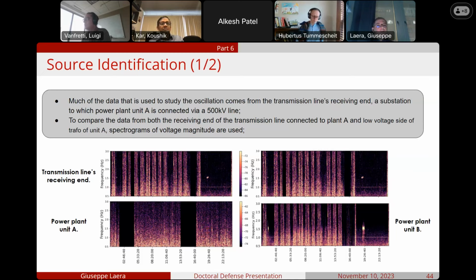So the idea to analyze the spectrogram of the voltage magnitude of unit B came out, and it was compared, as we can see here on the right, with the spectrogram again from the transmission line receiving end. And in this case, we can see how there is a bright spot here corresponding to 1.5 Hertz for unit B, and the other bright spot for the transmission line receiving end.